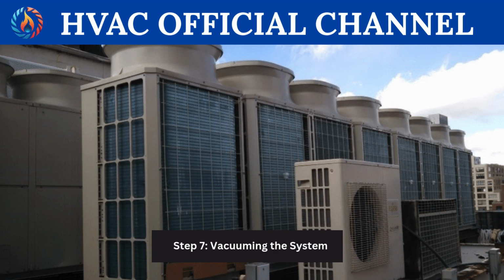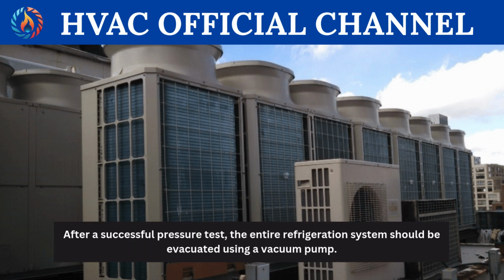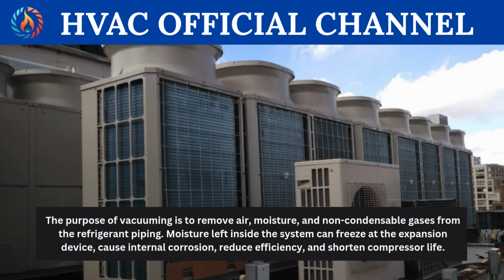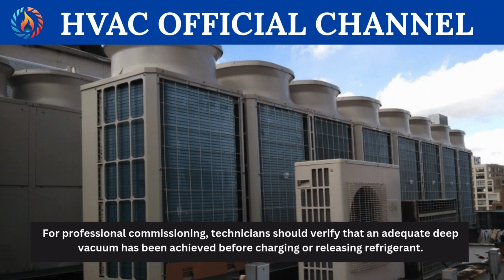Step 7. Vacuuming the system. After a successful pressure test, the entire refrigeration system should be evacuated using a vacuum pump. The purpose of vacuuming is to remove air, moisture, and non-condensable gases from the refrigerant piping. Moisture left inside the system can freeze at the expansion device, cause internal corrosion, reduce efficiency, and shorten compressor life. For professional commissioning, technicians should verify that an adequate deep vacuum has been achieved before charging or releasing refrigerant.